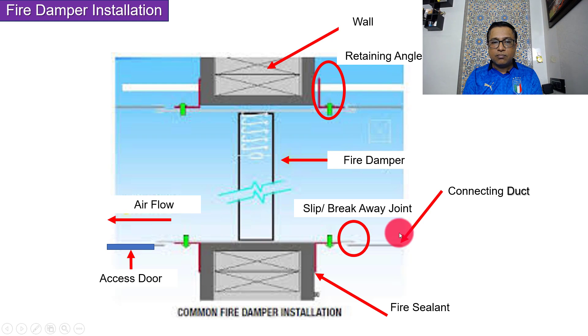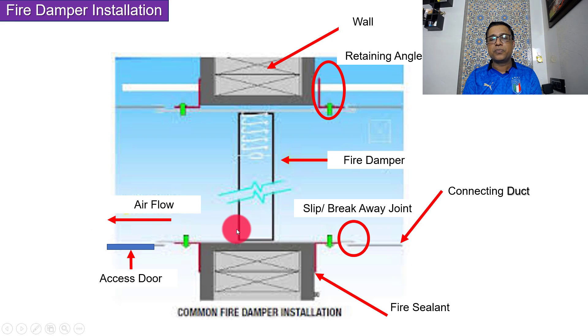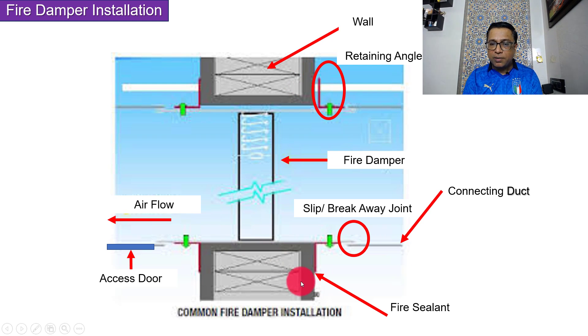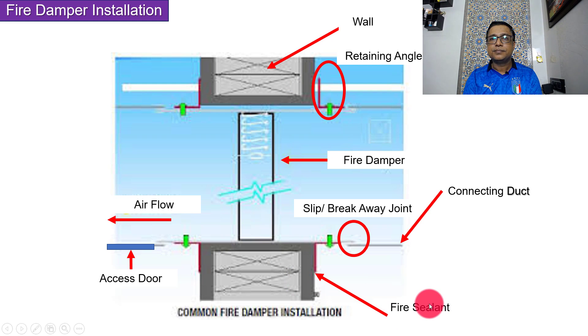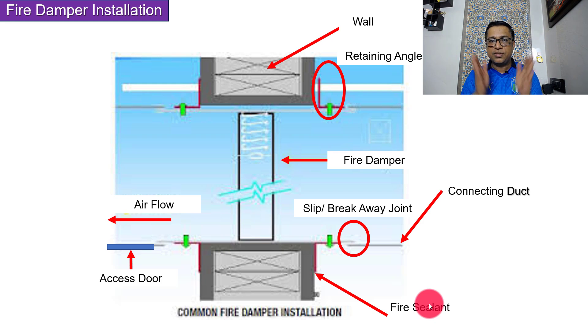We also need to look at the airflow through the connecting duct. The gap between the retaining angle and the wall must be treated with fire sealant. This is the correct way of installing a fire damper.